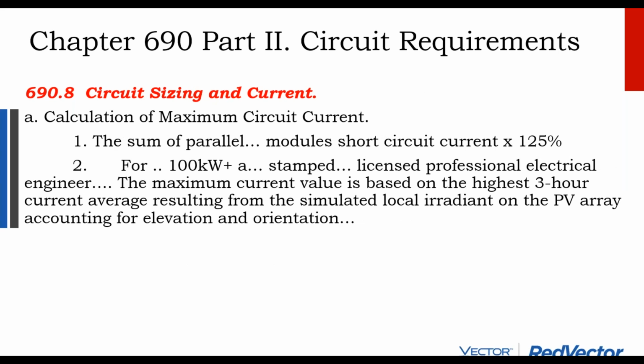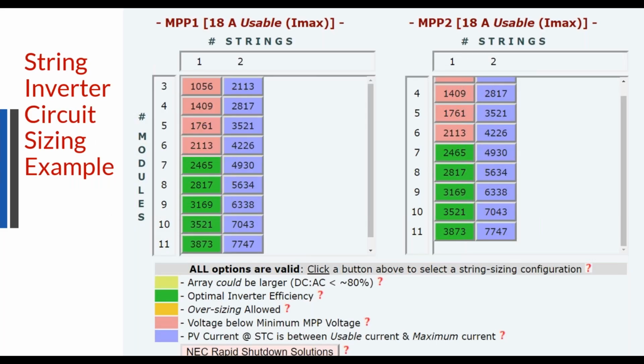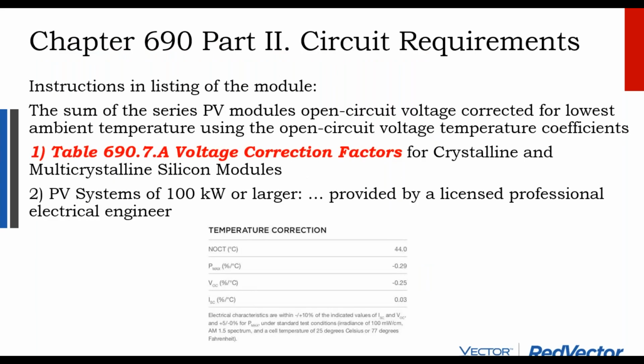What we're seeing here is basically you take, say for current, the number of parallel circuits, because in parallel your current is adding up, and then you add a 25% correction factor to it. Often, whether you're calculating the voltage with your temperature correction factors or calculating amperage, the main difference is that engineers can come in and say, well, actually, the coldest temperature on record happens at 3 a.m. at night, and the solar array is not going to be on by the time the sun comes up. It's no longer -40, it's -20. And so I'm an engineer signing off on the project. We can do the design around -20 instead of -40.